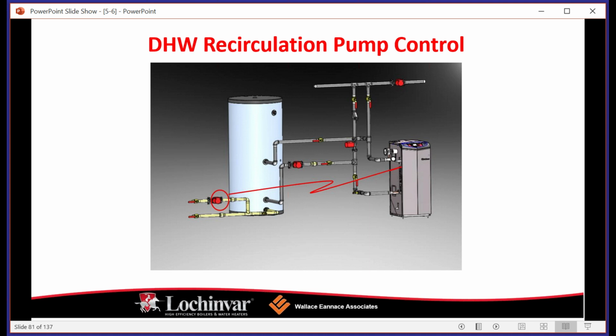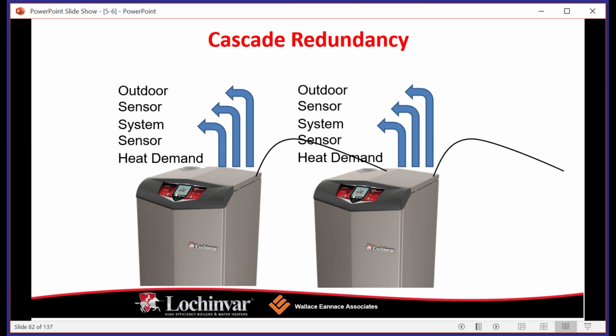Smart system, again, domestic hot water recirculation pump. You're going to have a low voltage terminal that's going to tell that pump when it needs to run and when it doesn't. Cascade redundancy. Okay, so all of the equipment that Lochinvar makes has the ability to run as a boiler plant. Okay, so you can link together multiple pieces of equipment and you're going to tell them that they're running as a plant now. You're going to set it up as a leader and a follower. And what's going to happen is you're going to have multiple pieces of equipment now running to satisfy a demand. And you're going to run a system sensor, which is landed on the manifold for the system on the outlet of the boilers, and you're going to run that back to the leader boiler, and it's going to tell the other boilers what their fire rate should be.